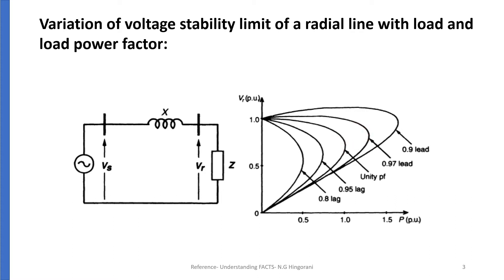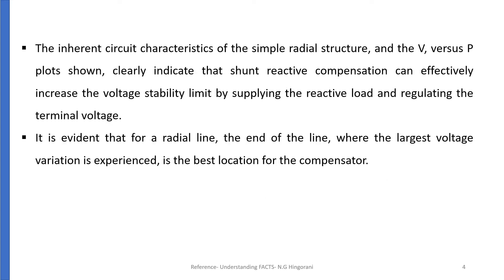This peak of the nose curve indicates the instability margin of the system. The inherent circuit characteristics of a simple radial structure and the PV plot clearly indicate that shunt reactive compensation can effectively increase the voltage stability limit by supplying the reactive load and regulating the terminal voltage. It is evident that for a radial line, the end of line — where the largest voltage variation is experienced — is the best location for the compensator.